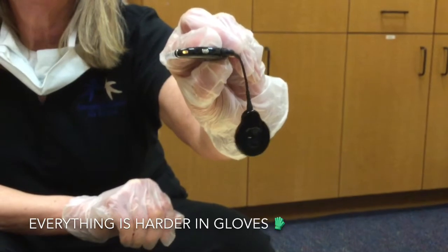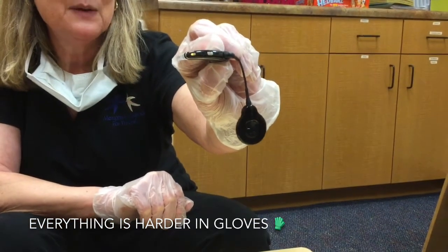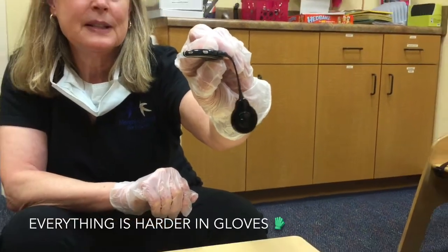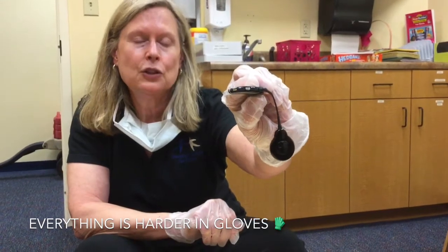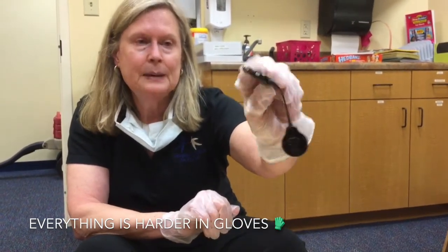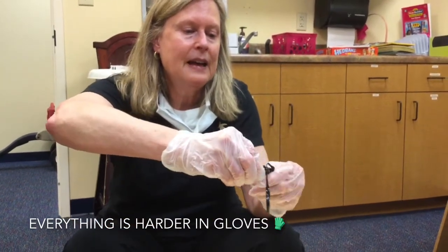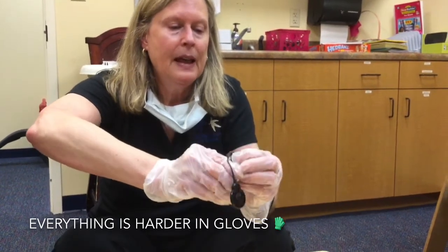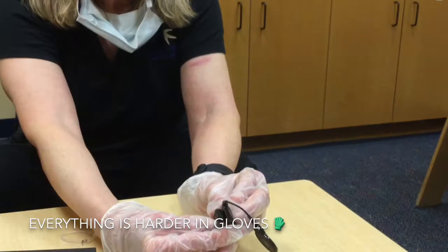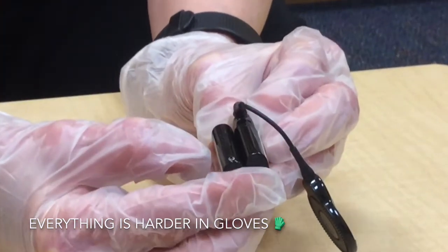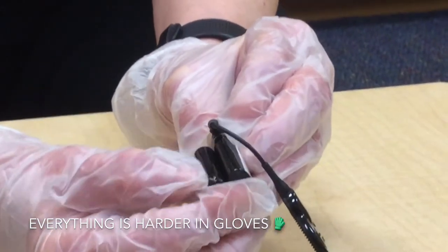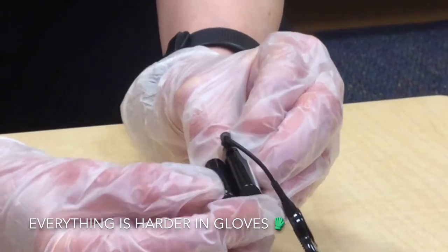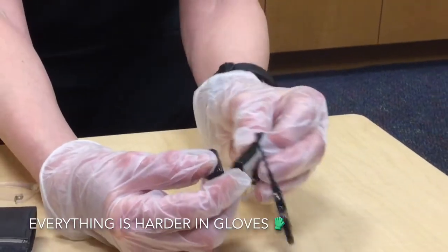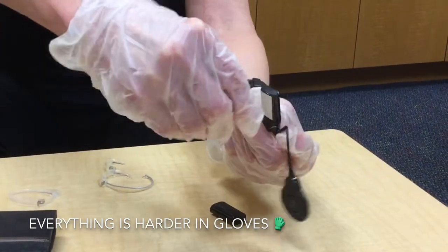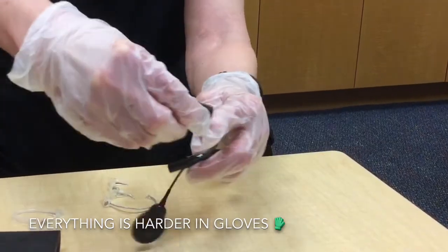You're seeing a slow orange flash. Imagine that about double the speed of blinking, and that tells you the batteries are bad for your child's processor. You'd want to either take a new rechargeable battery off the charger or put in new disposable batteries. The batteries just twist off and on. This is a rechargeable battery, and here is a disposable battery. For grandparents or caregivers, you can tell a disposable battery cover because it has holes in it, letting the zinc air battery get constant air access, since they won't work without it. The rechargeable battery cover is smooth all the way around compared to the disposable one.